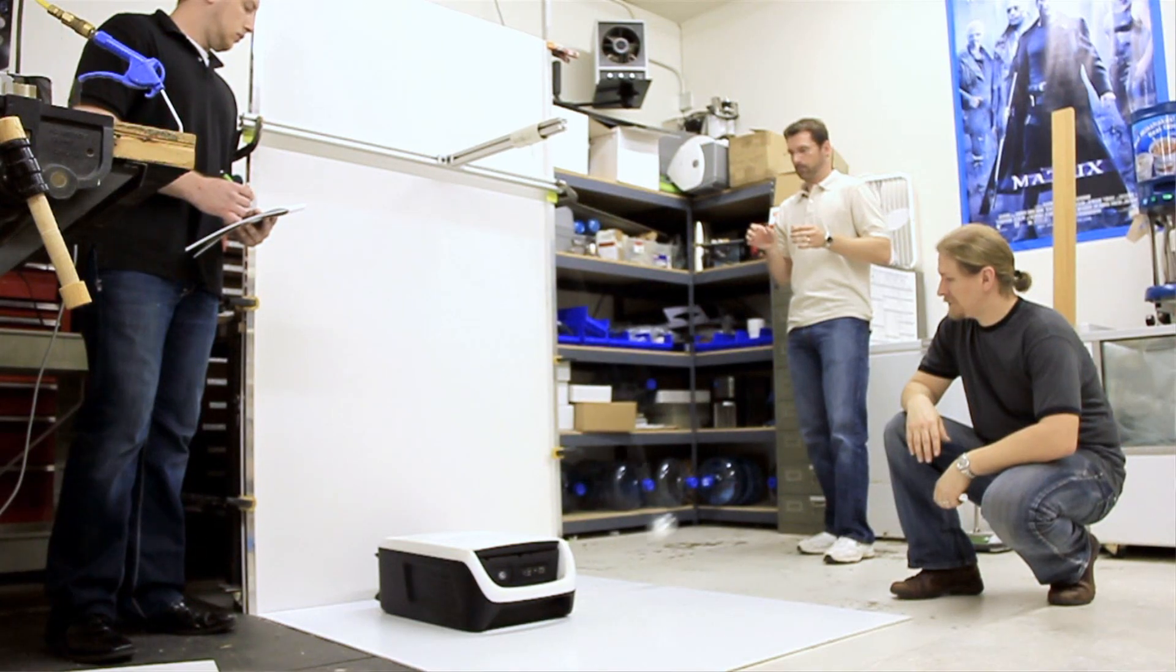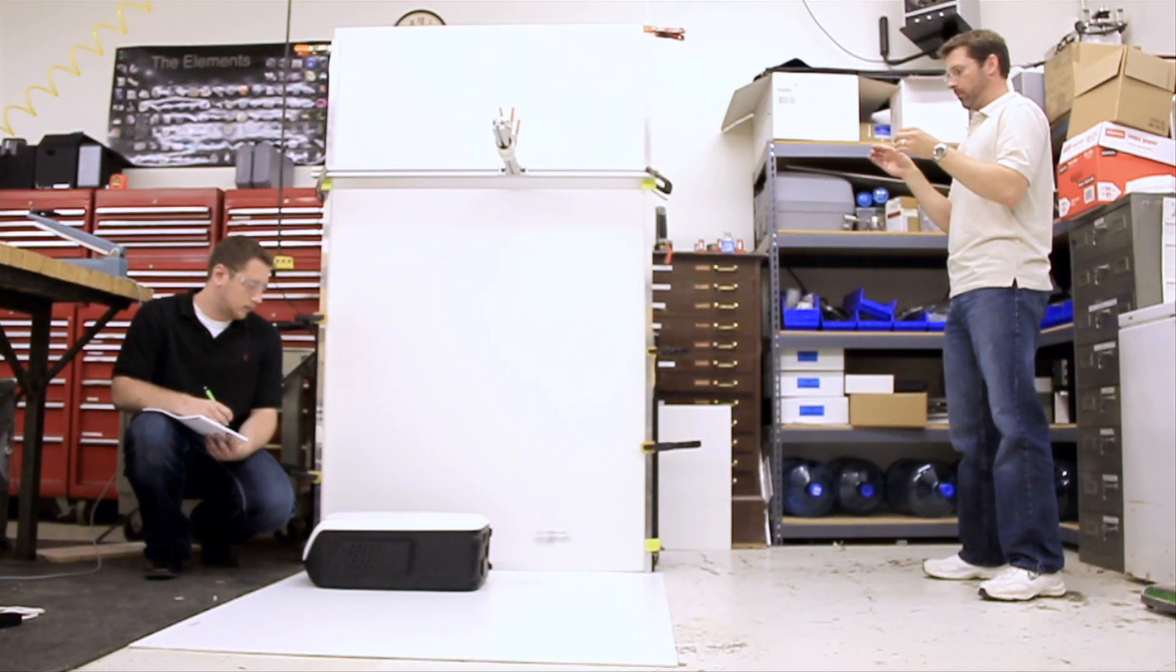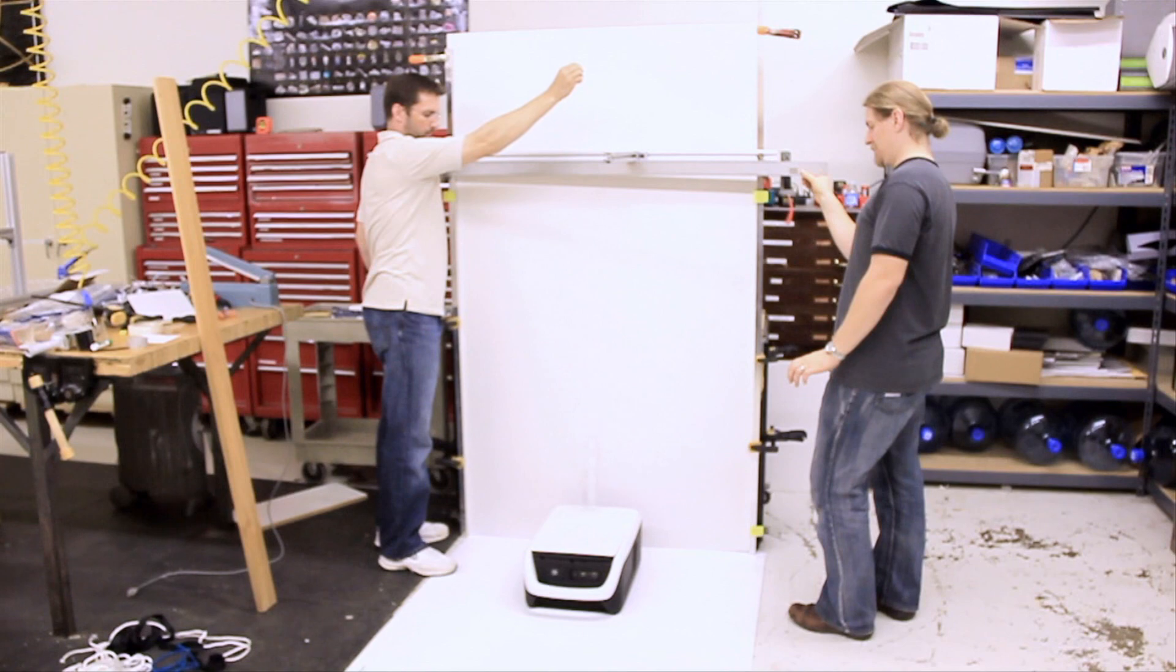We developed an impact ball that met the specification requirement for drop testing and impact testing. And we smacked it into the side of this product numerous times. Our goal was to try to either crack the FDM or break it within the normal use parameters. And it held up the whole way through. We were surprised to see the FDM perform so well. It beat all the tests with flying colors.